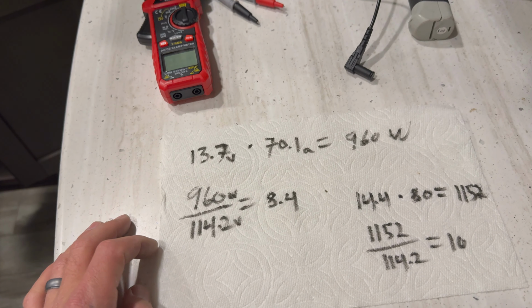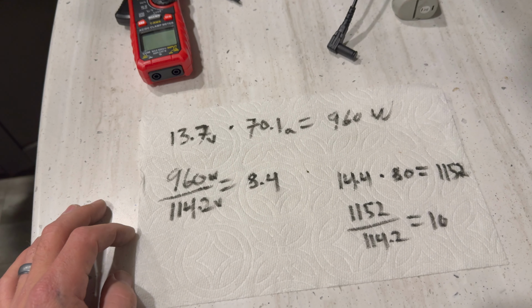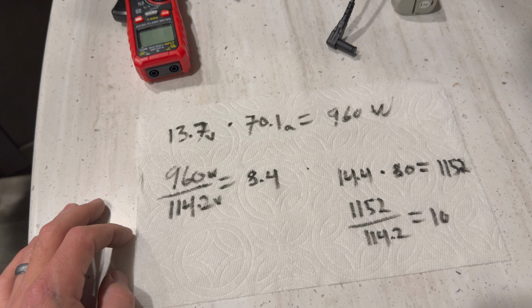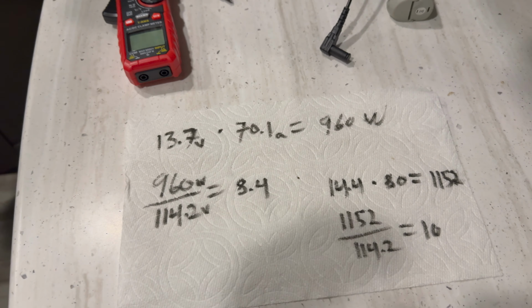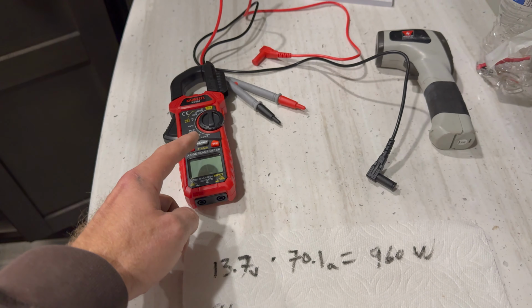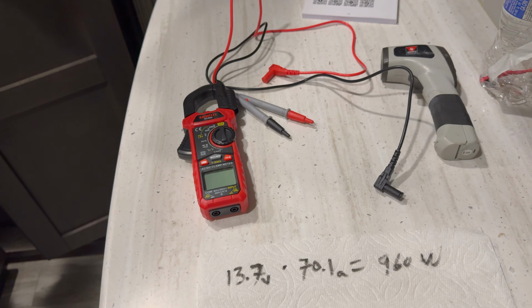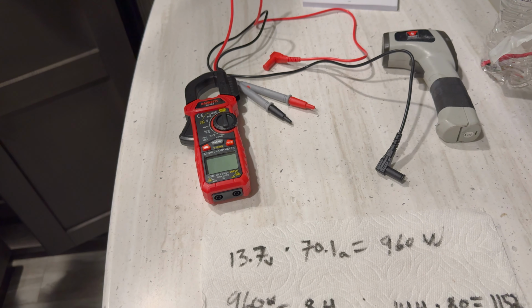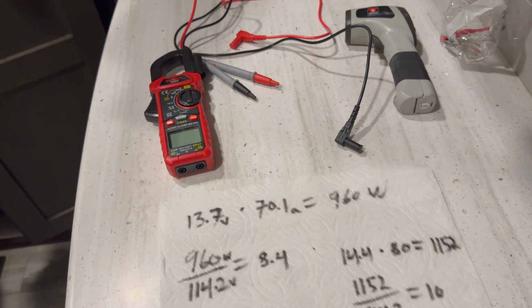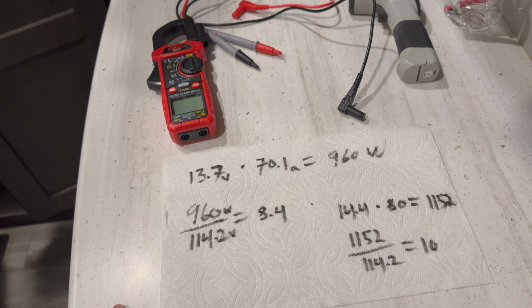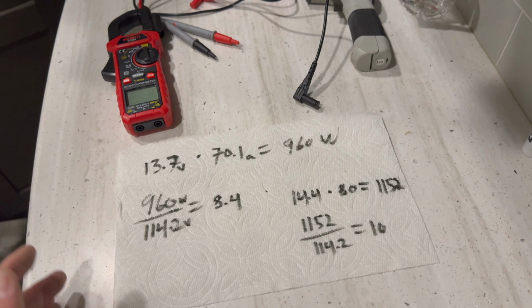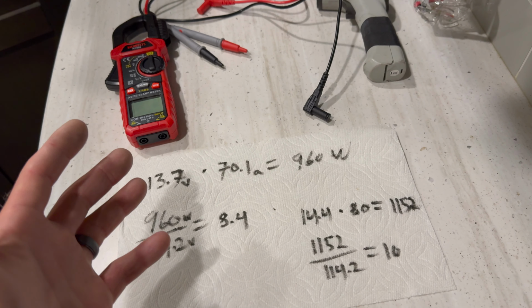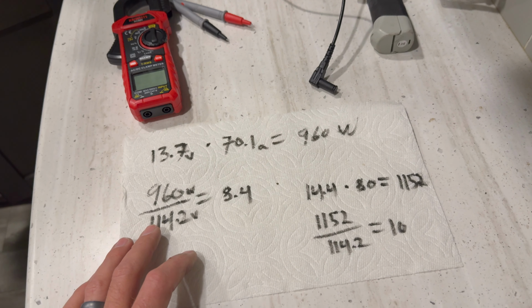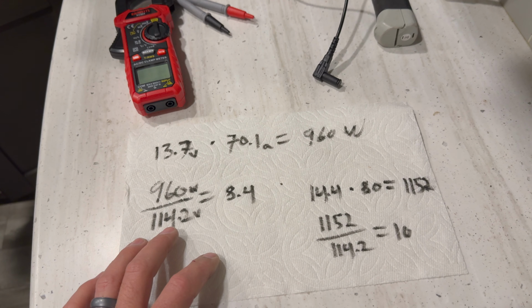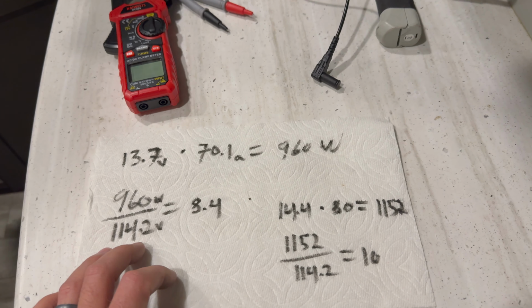Should theoretically be 8.4 amps placed on that converter circuit breaker, but as you saw, we measured 15.2. So the discrepancy between them, I don't know, I suppose it's the inefficiency of the converter, a little bit of heat loss, possibly this cheap Amazon fluke amp meter is maybe not as accurate. Maybe there's something else I'm missing, but in theory, that's what it should be. But we are doing 15.2, so I think I'm just going to go ahead and swap out that circuit breaker just so we don't have any trouble down the road.